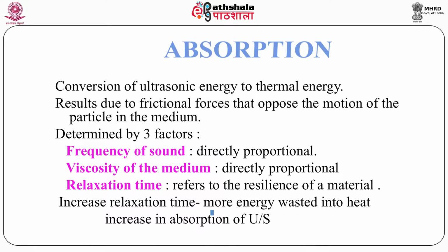Next type of interaction is absorption. It refers to the conversion of sound energy to thermal energy. The factors which determine the amount of absorption: first is the viscosity of the conducting medium. Absorption of the ultrasound wave is directly proportional to the viscosity of the conducting medium. Second is the relaxation time of the medium. An increase in relaxation time increases the absorption of the sound wave. Third is the frequency of the sound wave. So the higher the frequency, the more the absorption. Higher viscous liquid, more absorption. Higher relaxation time, more absorption. Higher frequency, more absorption.